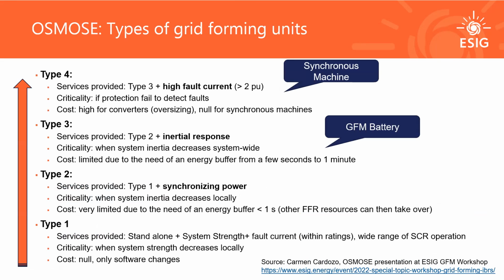I think what's interesting here is that they identified that grid forming inverters can be separated into 4 different groups depending on capability. So this is going back to the definition: what's grid forming, and can a core grid forming be defined, and then everything else is additional functionality that's added on top and just defines the hardware that you have. And so this type 1 grid forming is a basic grid forming. GE also calls it core grid forming, and that's the one that can ensure standalone operation, provide system strength, fault current within rating, and operate in a wide range of short circuit ratio.